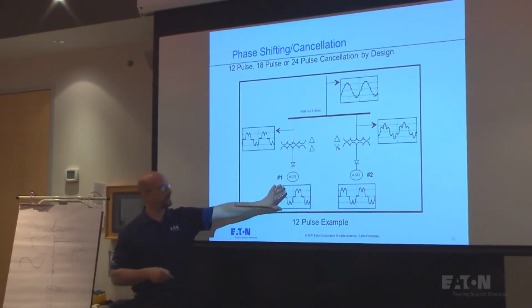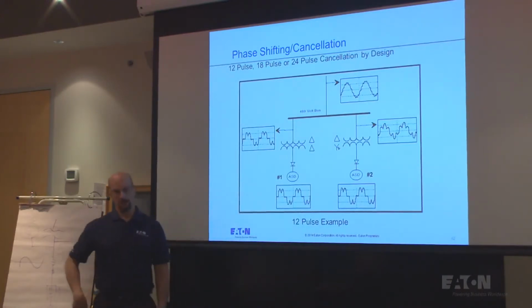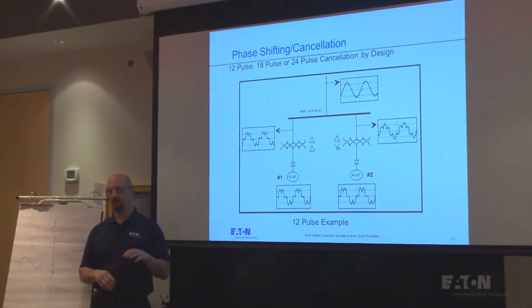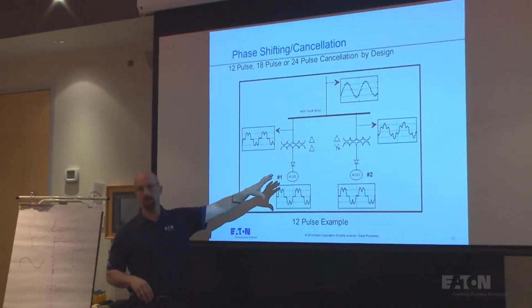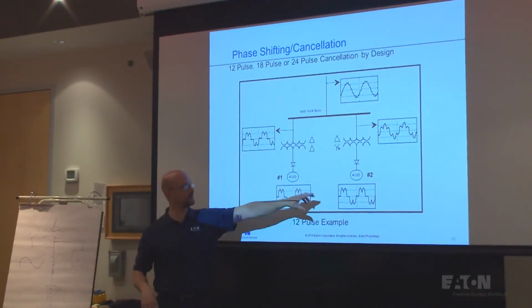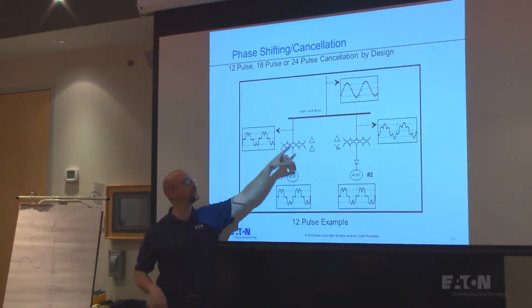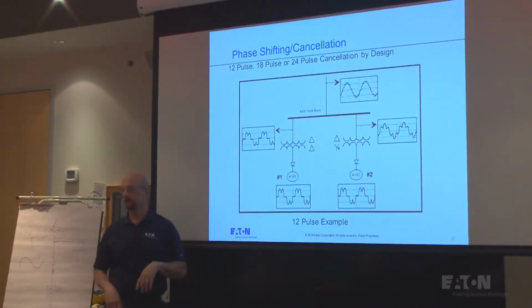Now, what if this drive's only running at half speed and that one's running at full speed? Now I don't cancel all the harmonics, but instead of adding, let's say this one produced, let's say I didn't do any phase shifting, 10 amps of fifth harmonic, 10 amps of fifth harmonic. I don't do any phase shifting. Up there I have 20 amps.